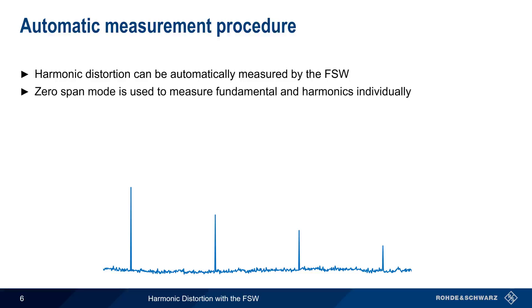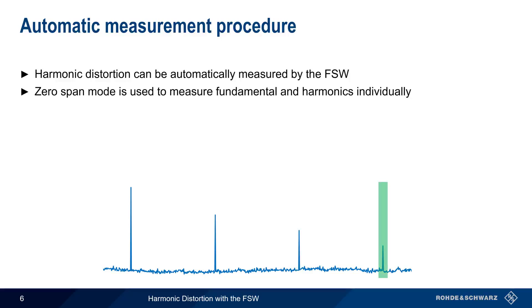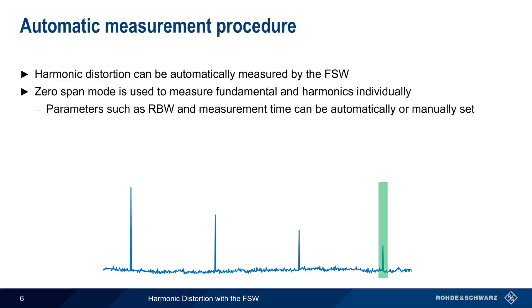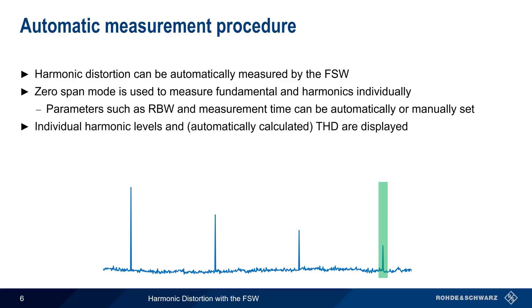Therefore, the FSW's automatic measurement procedure is recommended when measuring harmonic distortion. This function uses zero-span mode to measure the level of the fundamental and then each user-specified harmonic individually. Parameters such as the resolution bandwidth and measurement time can be either manually or automatically defined. At the end of the measurement, the FSW displays both the levels of the individual harmonics as well as the automatically calculated value of total harmonic distortion. In the remainder of this presentation, we'll go step by step through how to configure and use this automated measurement.